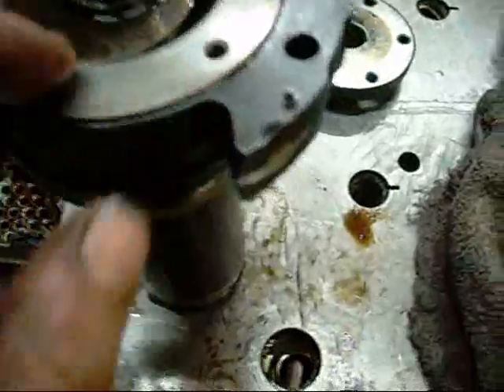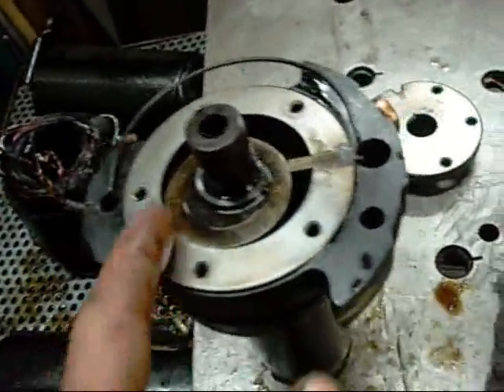There are a few score marks on the inside, but there's no obvious damage. Likewise on this bearing here and the main end bearing — it ran very hot but hasn't actually disintegrated. If anything, it was just dieseling the oil, creating all that blackness and smoke.